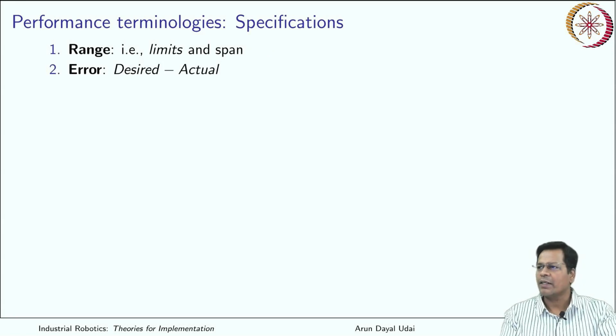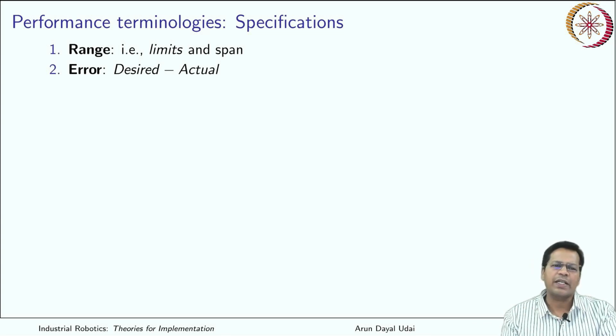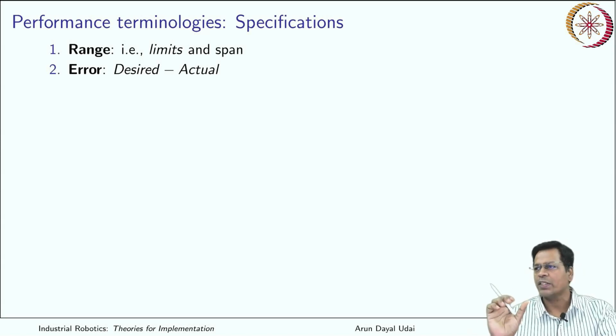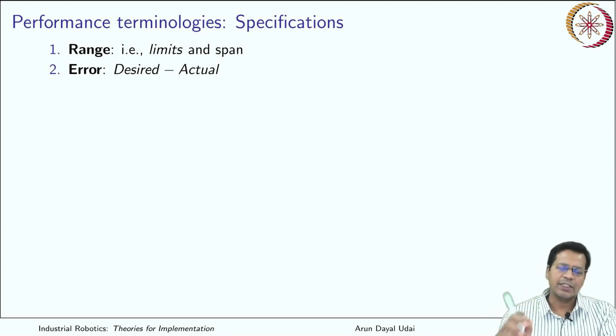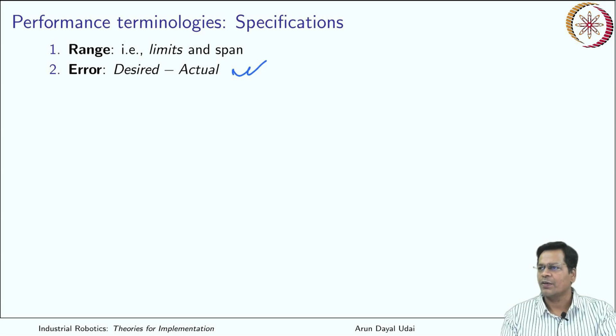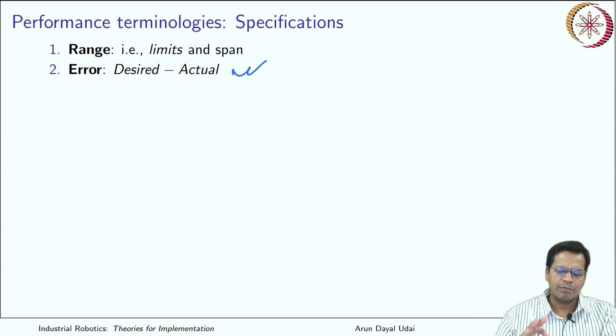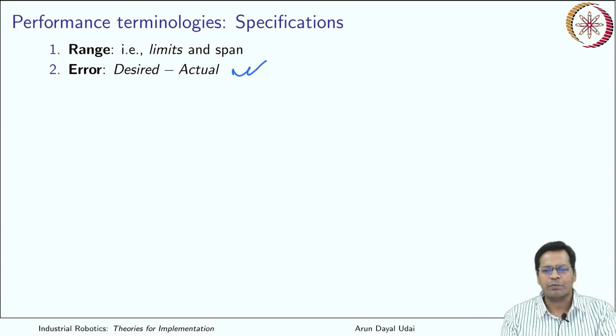And then error. Let's say this pneumatic pressure line is 6 bar, but it is showing 6.5 bar all the time. So the desired one is what it actually is, and the actual one is what your sensor is showing you. Desired minus actual is the error signal. Mostly your data sheet shows error can be plus minus 1% of the full scale reading. That means if it is 100 bar, it can show 99, or it can show 101 bar - that is the maximum error found through experiments.